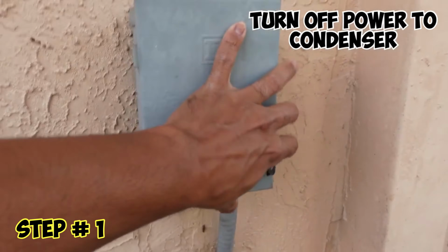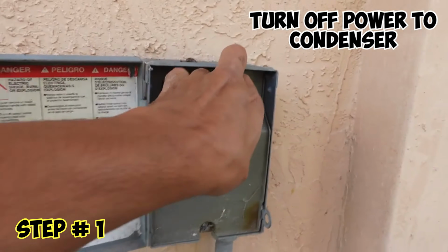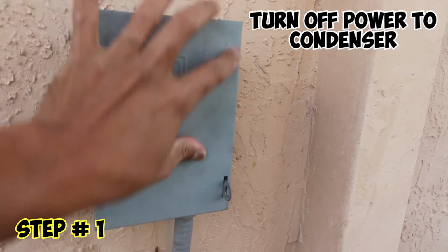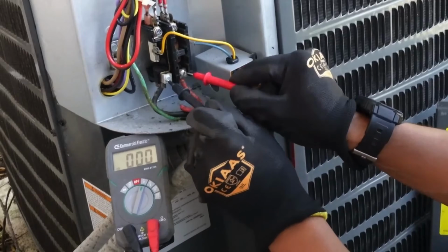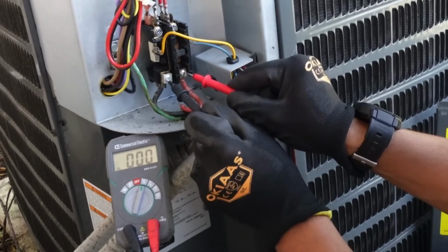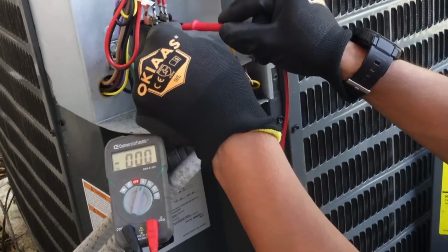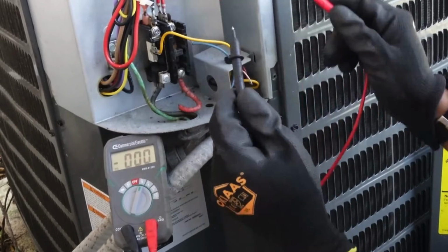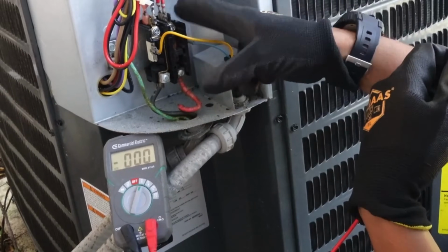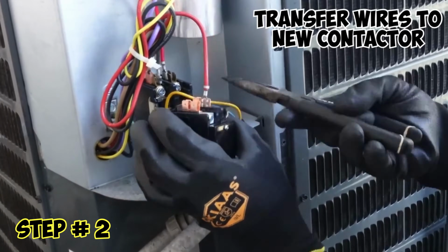Step 1, you want to cut the power off, whether that means turning off your breaker or your disconnect. Once your breaker is off, you want to test again on the base of your contactor where the power is coming in to make sure that you have 0 volts and that the contactor is dead. There's no power going to it.